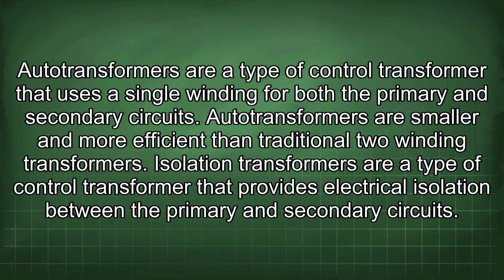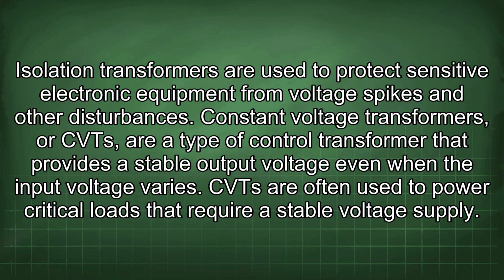Autotransformers are a type of control transformer that uses a single winding for both the primary and secondary circuits. Autotransformers are smaller and more efficient than traditional two-winding transformers. Isolation transformers are a type of control transformer that provides electrical isolation between the primary and secondary circuits. Isolation transformers are used to protect sensitive electronic equipment from voltage spikes and other disturbances. Constant voltage transformers, or CVTs, are a type of control transformer that provides a stable output voltage even when the input voltage varies. CVTs are often used to power critical loads that require a stable voltage supply.